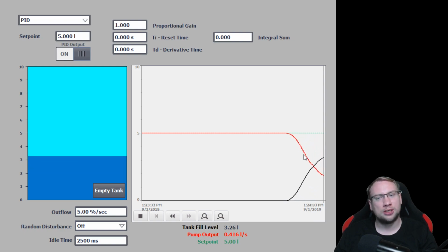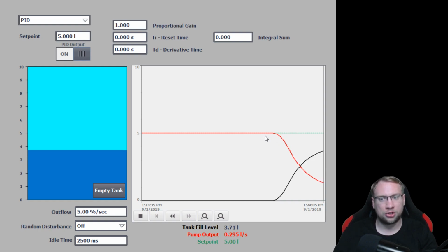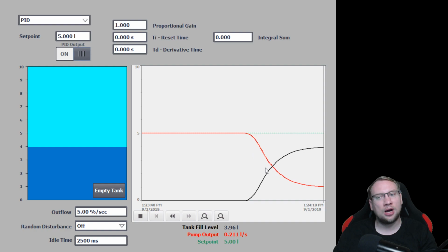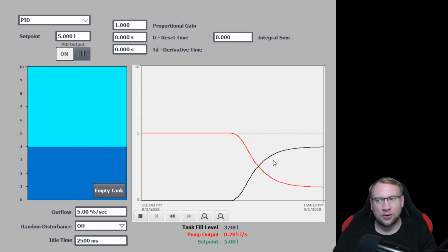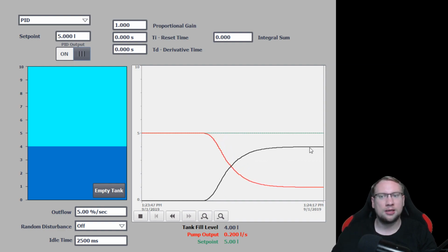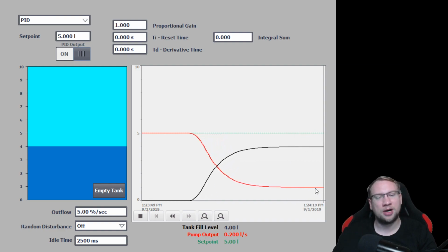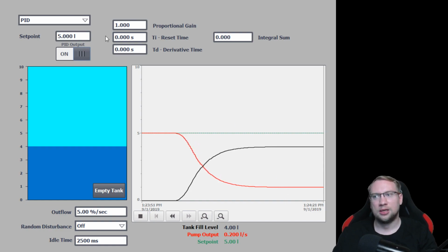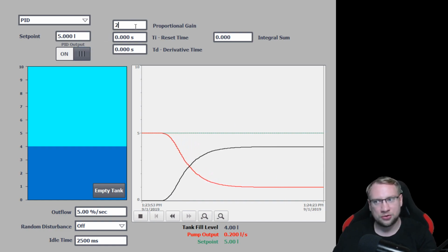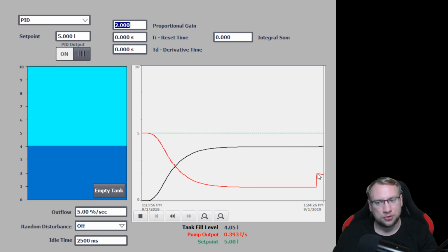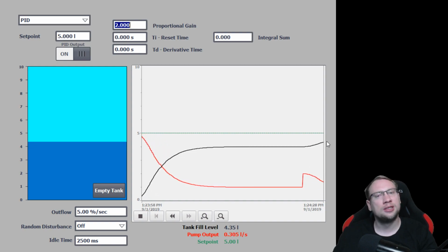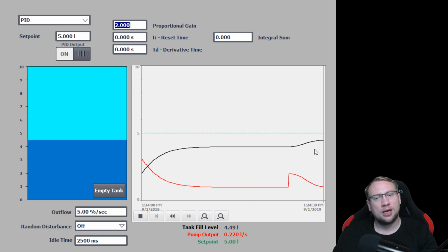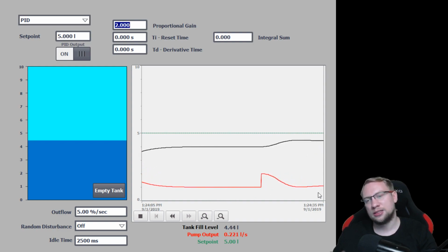And proportionally, really, that's why it's called proportional, right? A linear proportion here. My PLC output will react on that. So right now I have approximately 40% in my tank. The error is 10%, meaning my pump will be on for 10%. If I increase the proportional gain now to 2, you will see it jumps to 20%. The tank will be filled a little bit more, right? And we will be stuck again at a similar value.